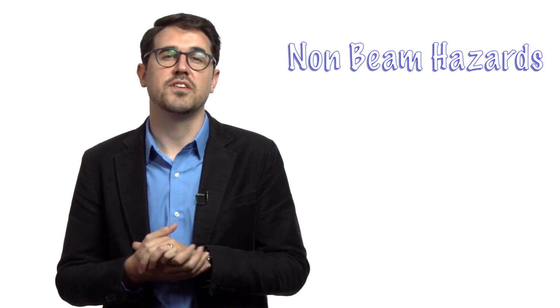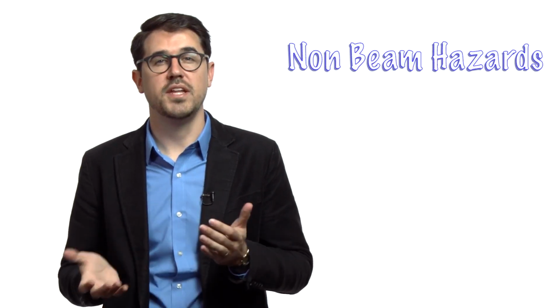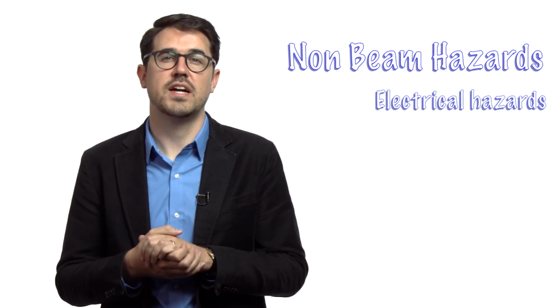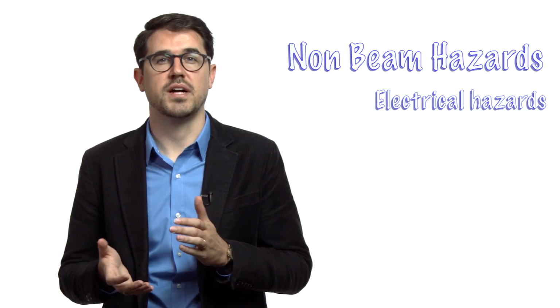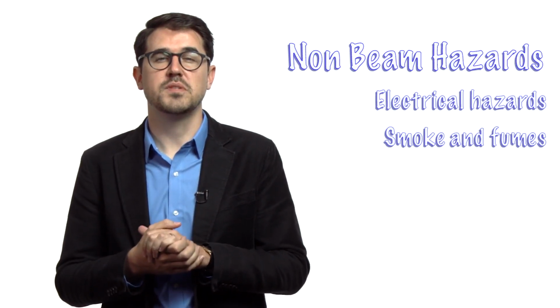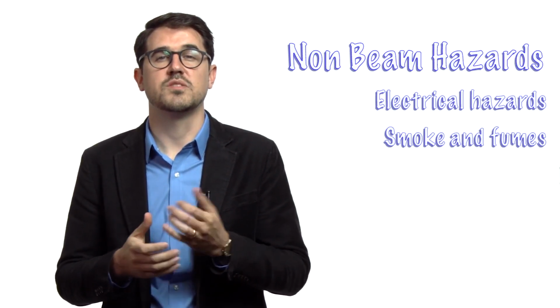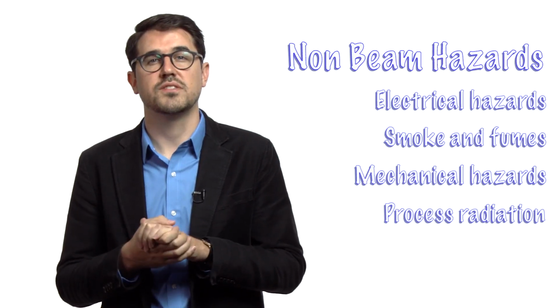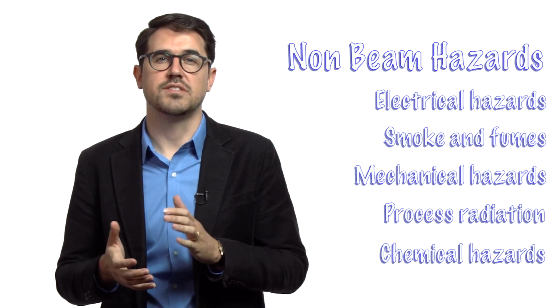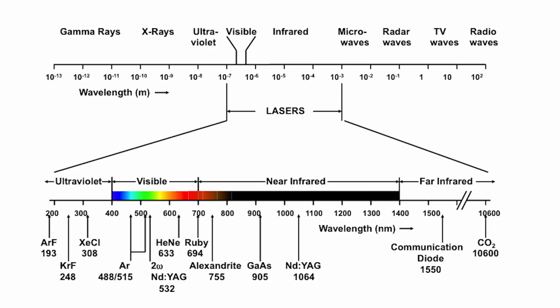Beam exposure is not the only hazard in a laser lab. Depending on your setup, you can have electrical hazards from high voltage power supplies. Smoke and fumes can be generated by the laser, as well as mechanical hazards, process radiation, and chemical hazards if you're using dye lasers. Lasers operate in the ultraviolet, visible, near-infrared, and far-infrared regions of the electromagnetic spectrum.